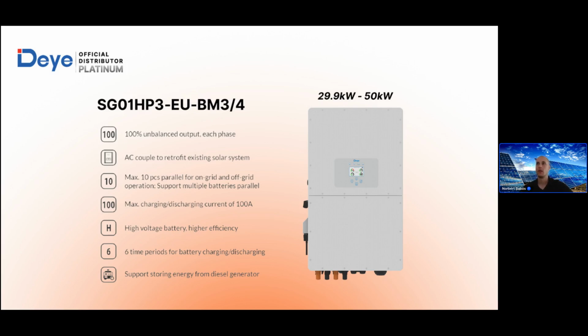It's also 50 kilowatt, 50% unbalance. So for the 50 kilowatt, you can reach 25 kilowatt peak power on a single phase in off-grid mode or in grid mode. It also has the EPS function, so you can have an EPS load connected to the inverter, and it will switch in between the sine waves, so you won't notice the grid goes off.